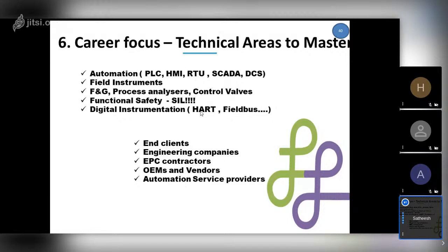Field instruments is another area. When we say field instruments, it is not fire and gas. Field instrument is basically pressure, flow, level, temperature, all the process parameters you're trying to measure in instrumentation. It's quite a nice area to cover as well, because automation is also not redundant without instrumentation, meaning instruments, the PLC, and all the systems like SCADA together act like a complete instrumentation.